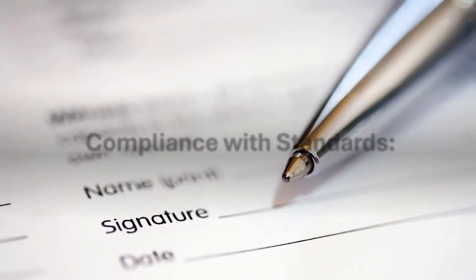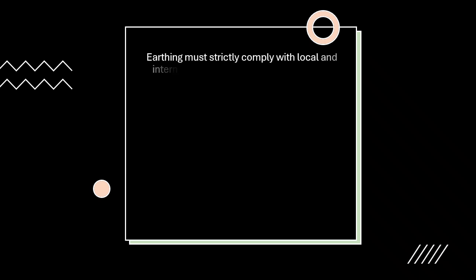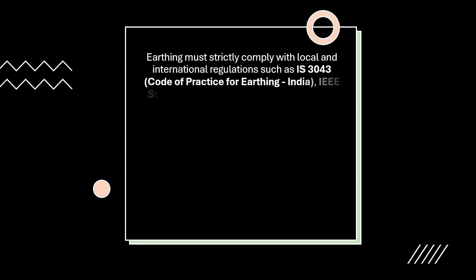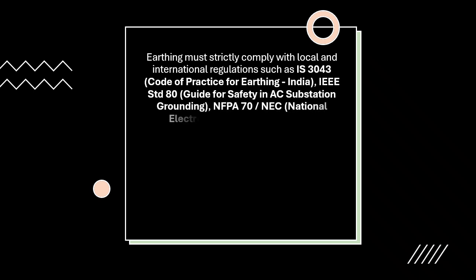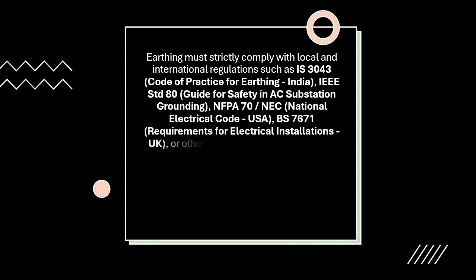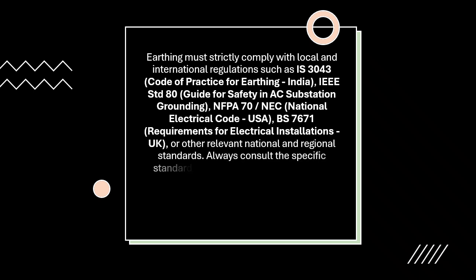Compliance with standards. Earthing must strictly comply with local and international regulations such as IS 3043, Code of Practice for Earthing, India, IEEE Std 80, Guide for Safety in AC Substation Grounding, NFPA 70, NEC, National Electrical Code, USA, BS 7671, Requirements for Electrical Installations, UK, or other relevant national and regional standards. Always consult the specific standards applicable to your jurisdiction.